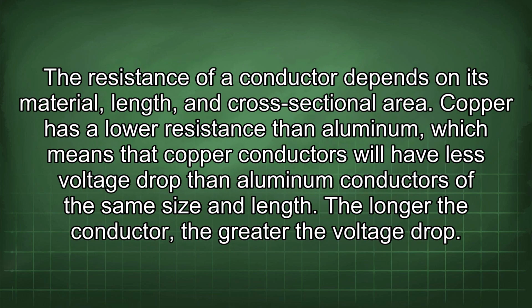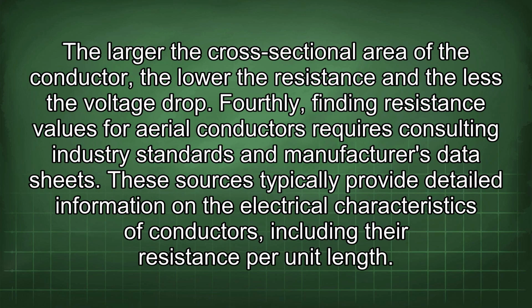The resistance of a conductor depends on its material, length, and cross-sectional area. Copper has a lower resistance than aluminum, which means that copper conductors will have less voltage drop than aluminum conductors of the same size and length. The longer the conductor, the greater the voltage drop. The larger the cross-sectional area of the conductor, the lower the resistance and the less the voltage drop.